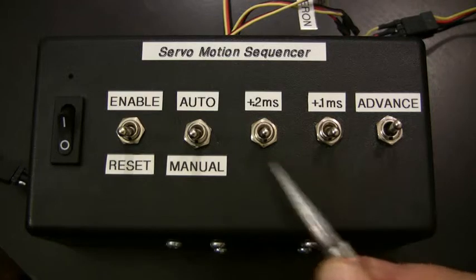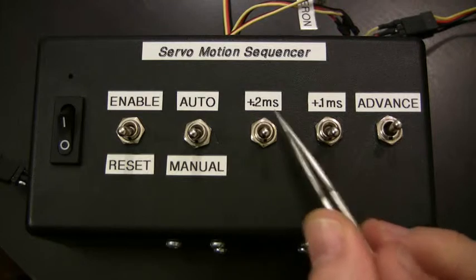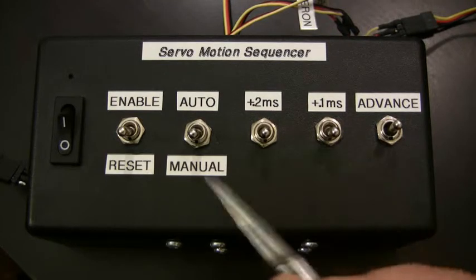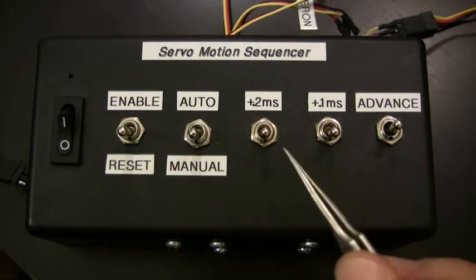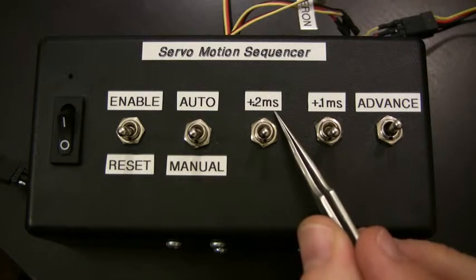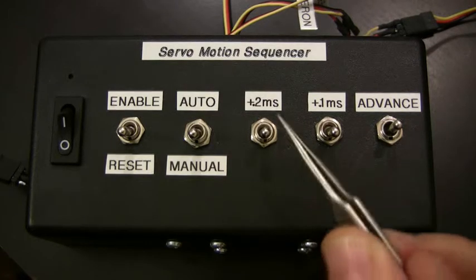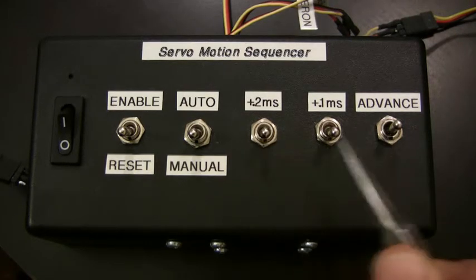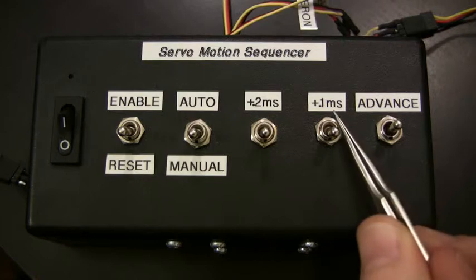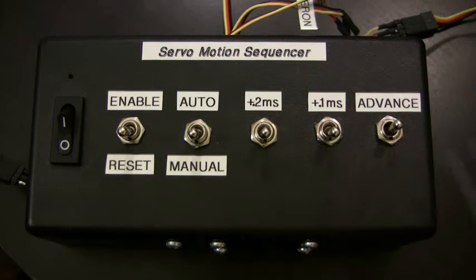These two switches work together. They are essentially a binary combination of additive pulse that give variable deflection magnitude. In this case it's plus 0.2 milliseconds and this is defined as the half amplitude. So enabling the switch adds control deflection and enabling the switch adds half of it, and they can be enabled together to give plus 0.3 milliseconds.